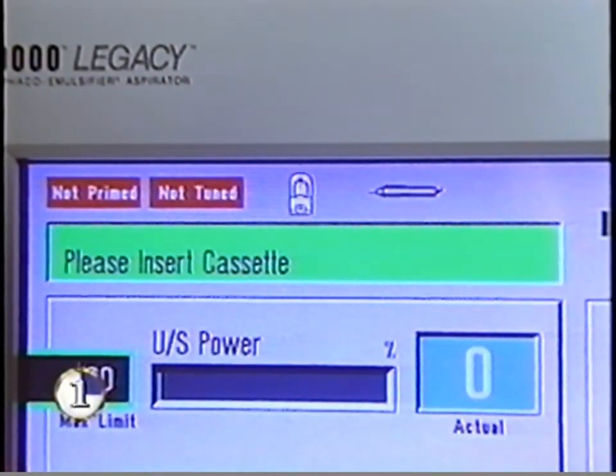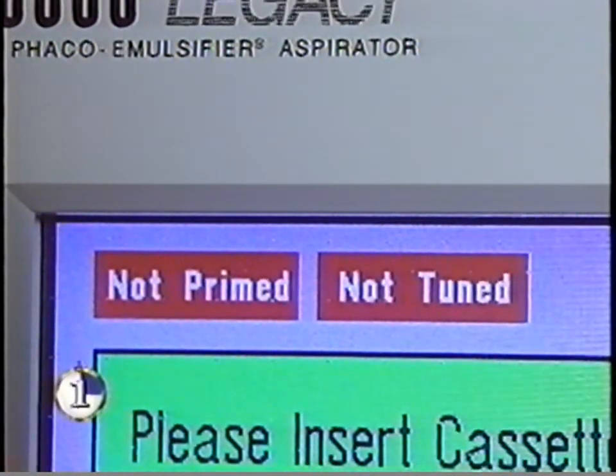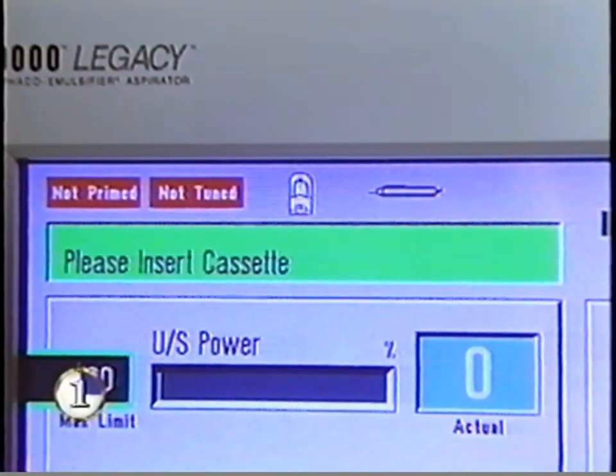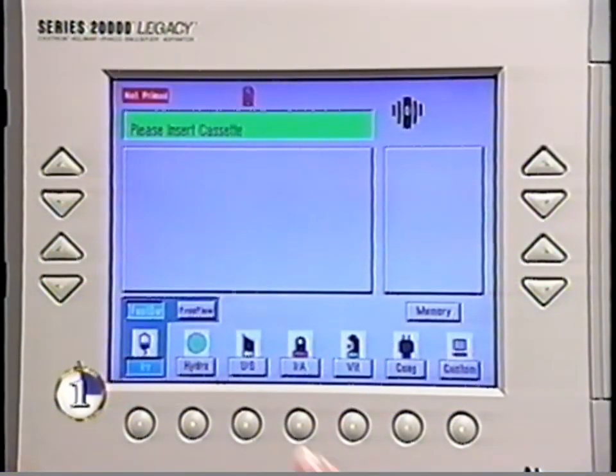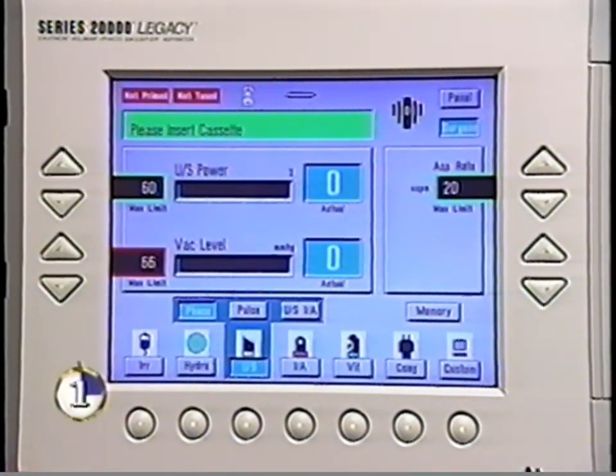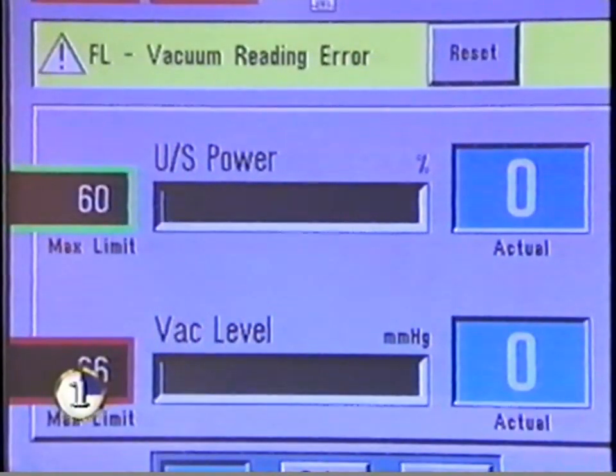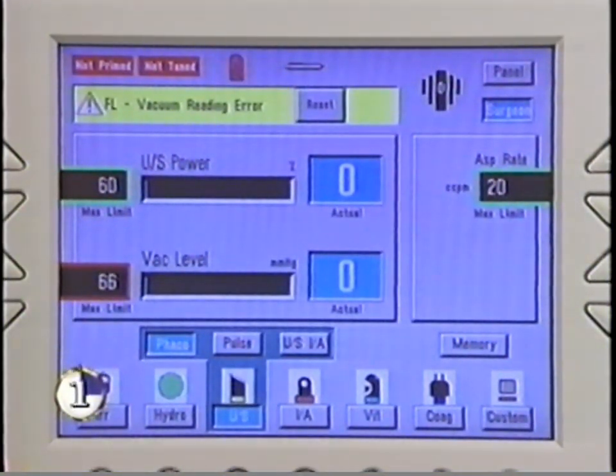At the top of the touchscreen, two windows inform the surgical team of the unit's status and potential problems. The text window indicates modes, submodes, and general messages during normal operations. It also displays average ultrasound power levels when the ultrasound phaco mode is in use. Watch the text window for such messages as faults, errors, and advisories, status reports during setups, and status icons for ancillary equipment such as handpieces and the foot switch.